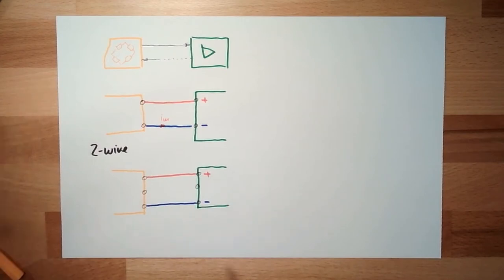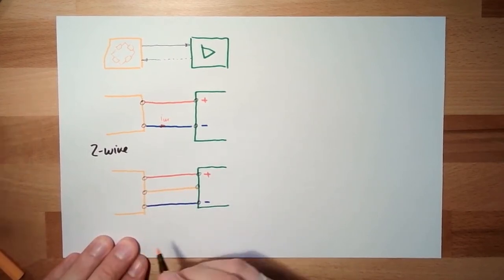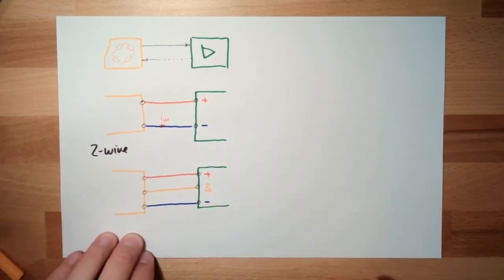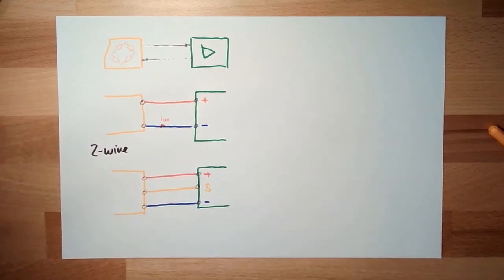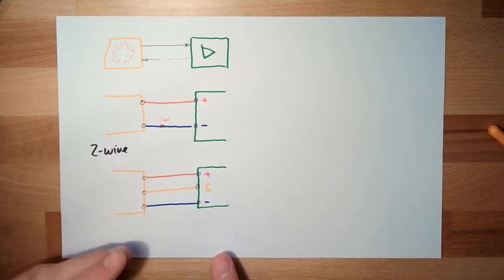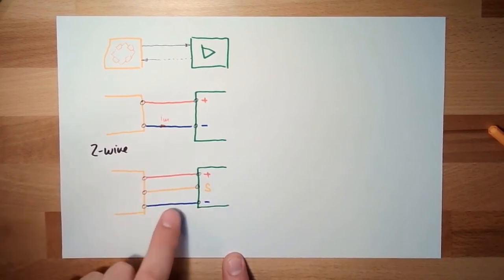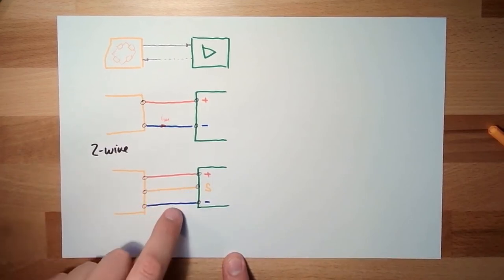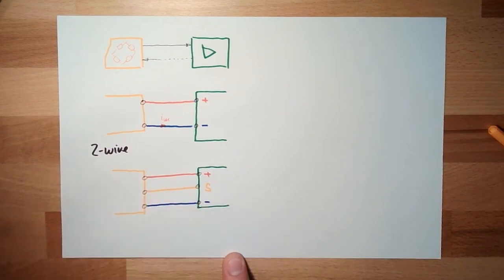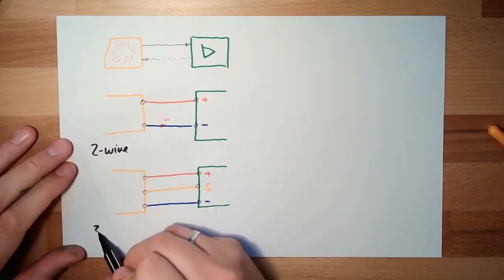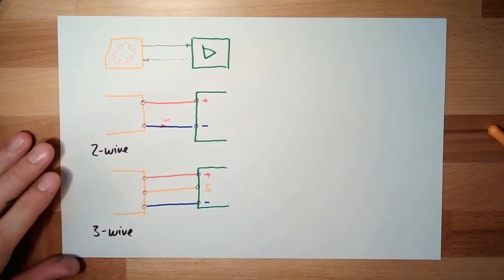And then here, I do have a signal. The sensor is having a third option, a third cable, where it gives back the signal. This now can be voltage. So the signal and the power supply have the same reference, ground. So this can be a voltage signal, or it can be a current signal as well. This thing here is logically called three-wire. Three-wire connection. There's still a common ground.